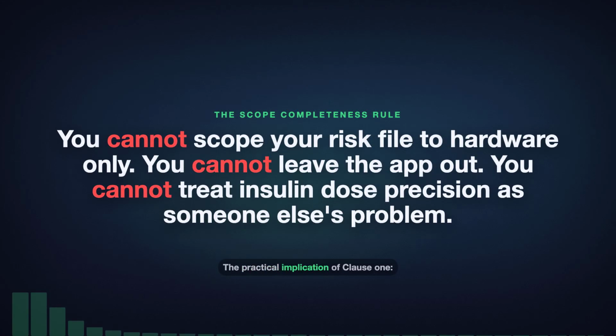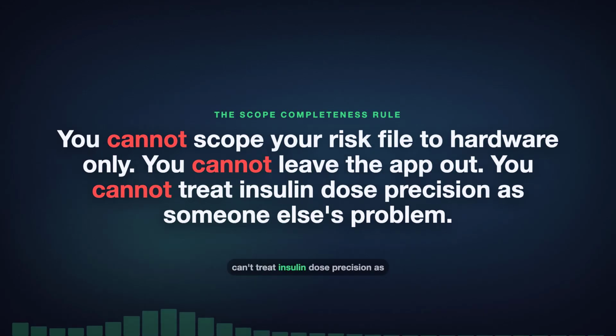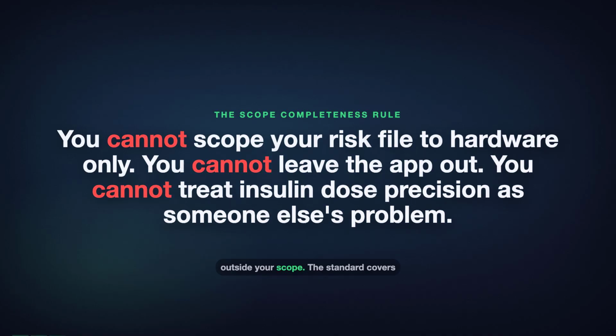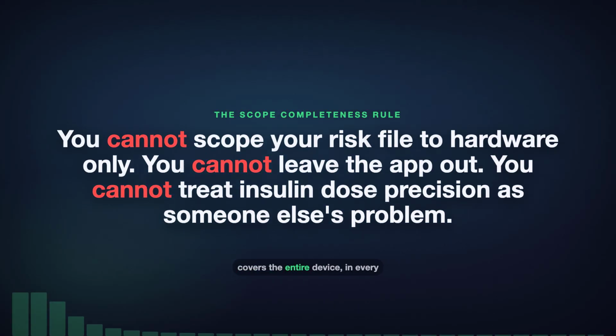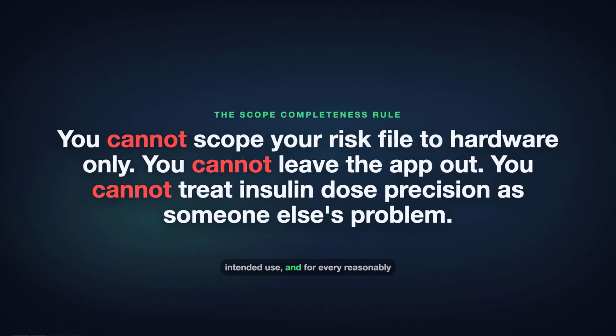The practical implication of Clause 1: you can't scope your risk management file to the hardware only. You can't leave the companion app out because your software team is managing it in a separate system. You can't treat insulin dose precision as a pharmacy problem outside your scope. The standard covers the entire device in every configuration, across every intended use, and for every reasonably foreseeable misuse.